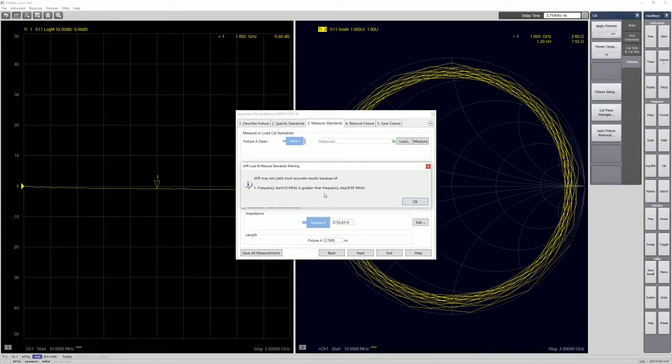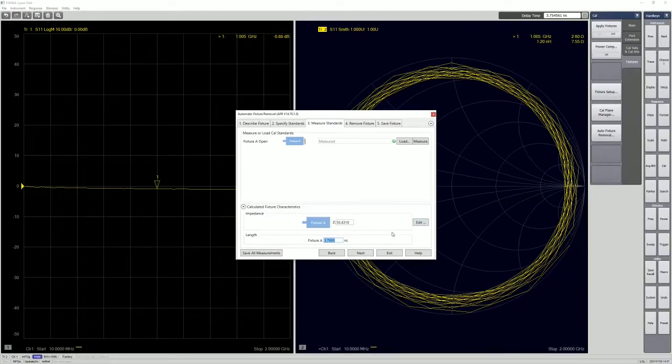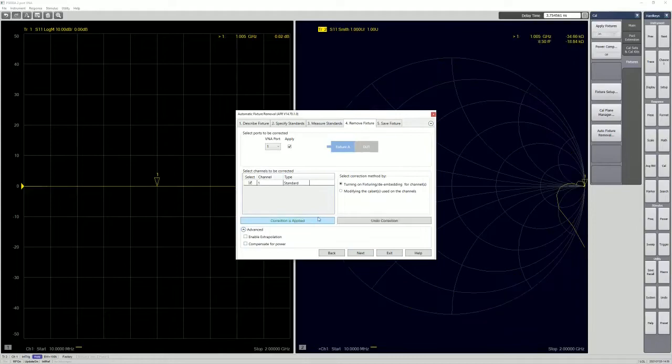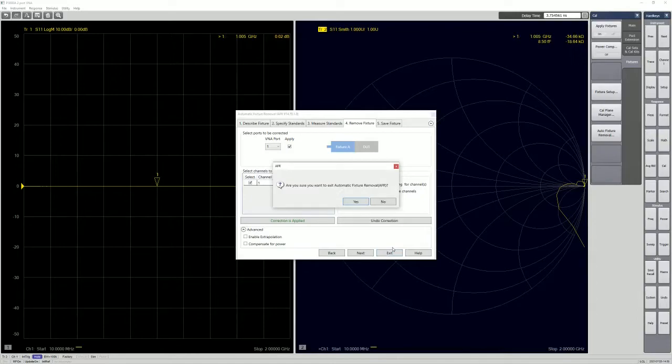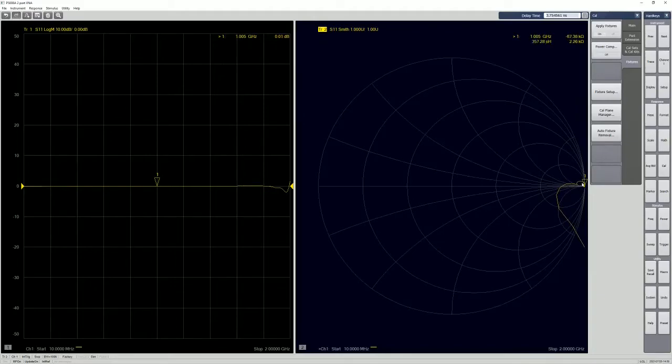So for me, just ignore it for now. So it's about right. 3.76. If you look at the previous one in the port extension, it's about 3.75-ish. So we just click next with that, and then apply corrections. Now you can see that there's something wrong with here. Let's exit it, but it's still applying. So you see that there's an unwanted tail here over this side.